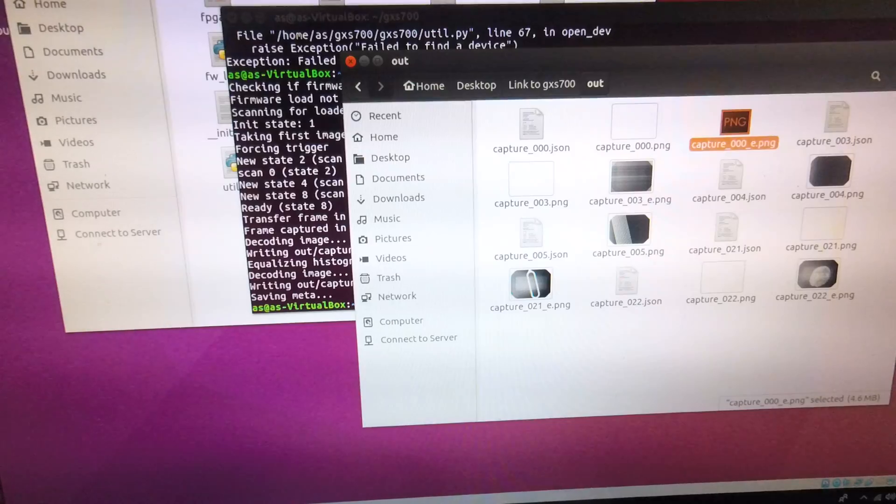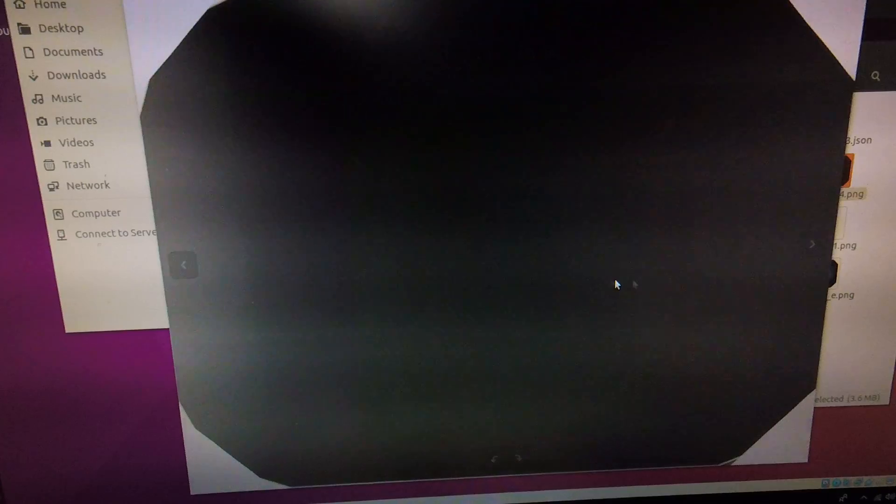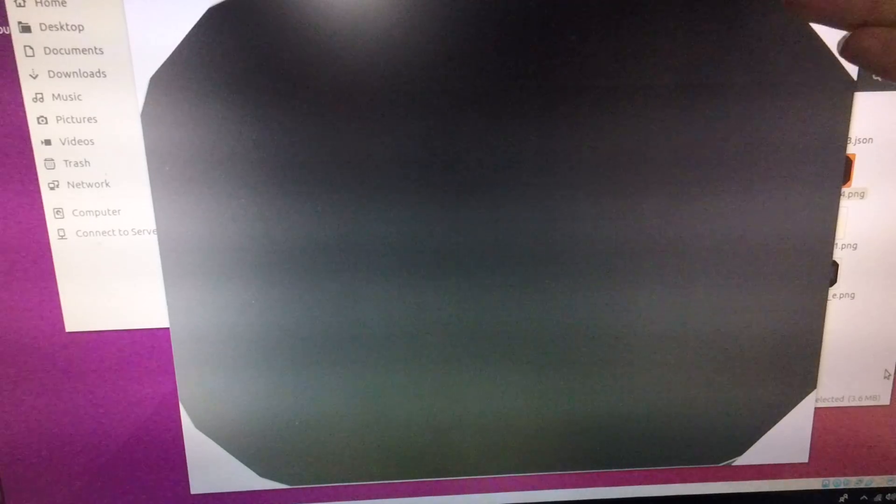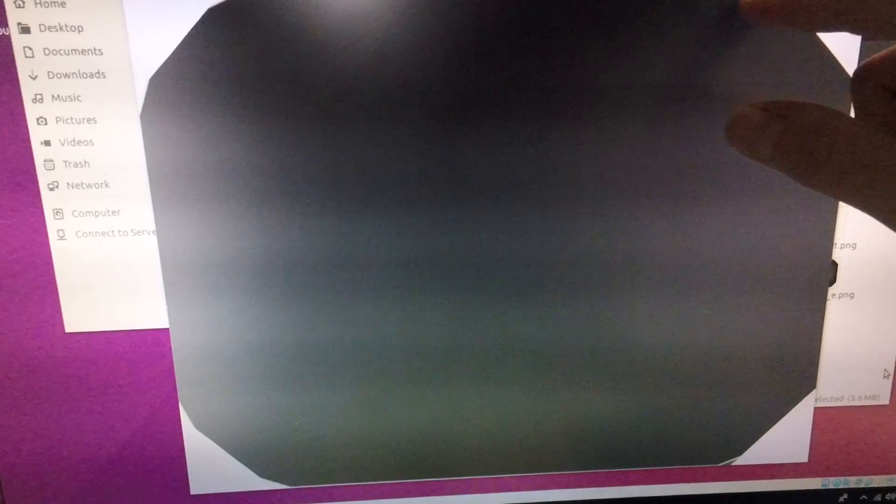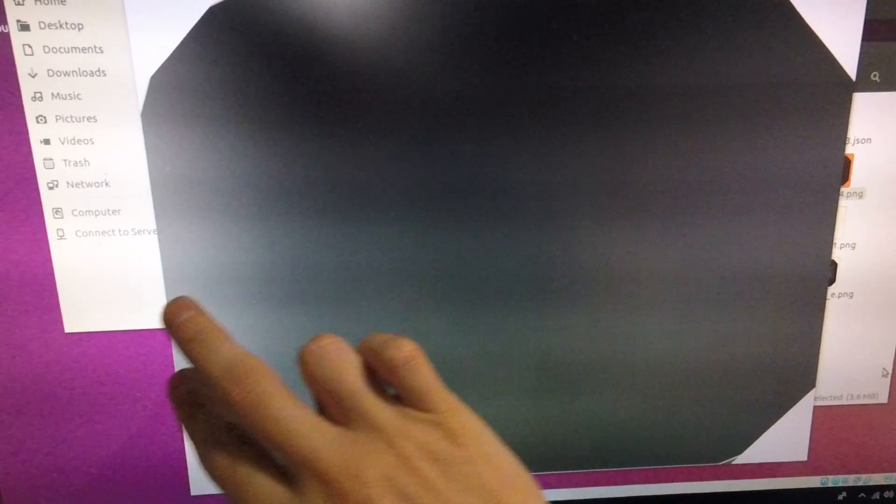Now if you were to expose this to x-rays for the flat field, I just put one of these sensors in the Faxitron x-ray unit and expose it to 35 kV energy x-rays. This actually I believe is the DEXIS Platinum sensor not the GENDEX sensor but they're basically the same thing other than a minor difference in the corner. But you can see that the sensor exposure is basically just all darkened.